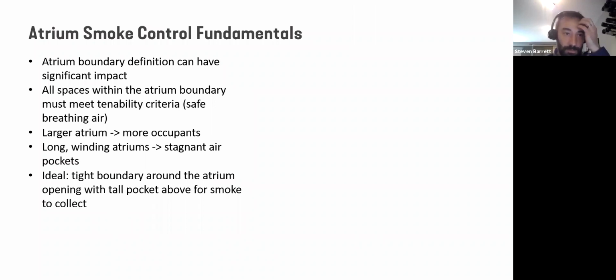So some important takeaways on the atrium smoke control are that the boundary definition itself can have a really significant impact. And it's arbitrary where we determine the atrium boundary to be. It can really affect the tenability criteria because there can be more occupants in the space. If the atrium is kind of long and winding, there can be some difficulty with air and stagnant pockets, where it can be difficult to actually continue to exhaust the smoke while making up fresh air. So if possible, it's best to keep the atrium boundary tight and tall so that there is a pocket for the smoke to collect in before it starts to descend and become a hazard to occupants.